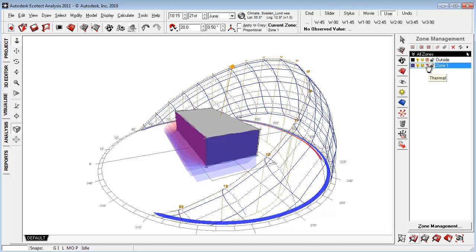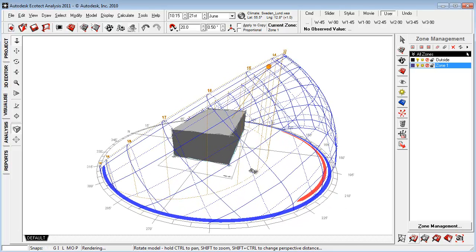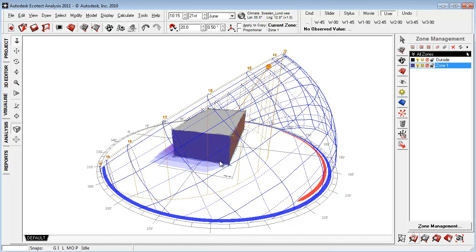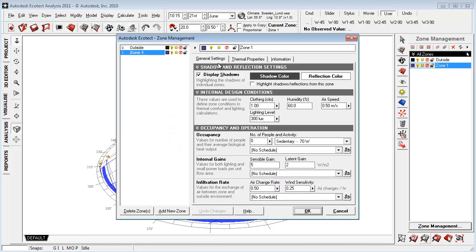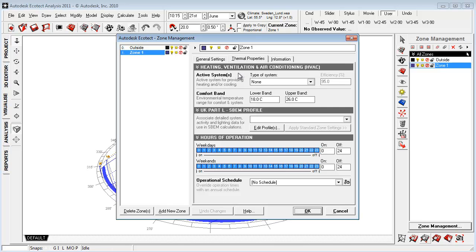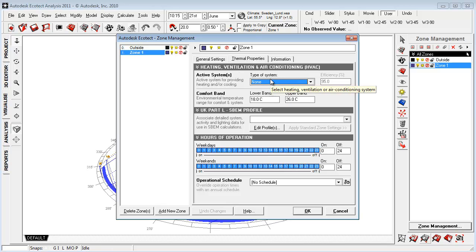If it's a thermal zone, it will be part of the thermal calculation. If it's not frozen, if it's not a thermal zone, it will only generate shadows or overshadowing for the thermal analysis. If we go to zone management here, we can go in and edit the internal design conditions, operation, occupancy, thermal properties to set up the system that we're working on.